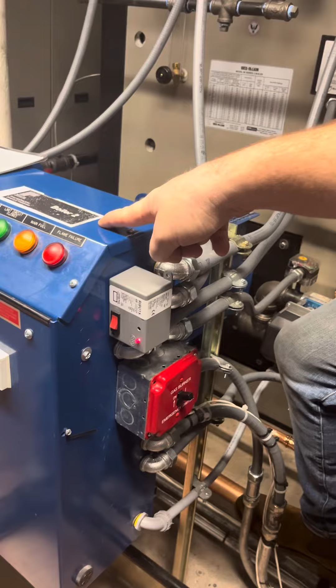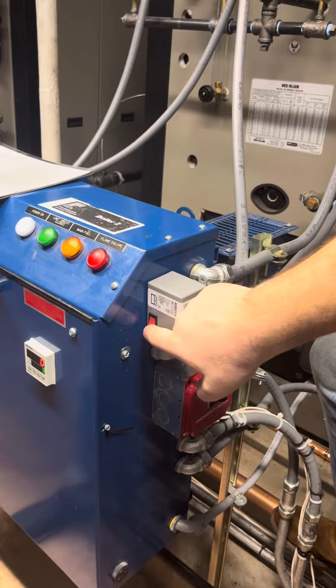So you're closing the contact into the boiler here. Got it. But now the only thing that's going to shut this boiler down is its own limit switch. But this should be down here in auto, for the BMS system to be able to control these.